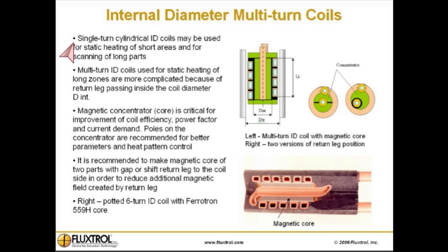Internal diameter multi-turn coils: single-turn cylindrical ID coils may be used for static heating of short areas and for scanning of long parts. Multi-turn ID coils used for static heating of long zones are more complicated because of the return leg passing inside the coil diameter. A magnetic concentrator or core is critical for improvement of coil efficiency, power factor, and current demand.